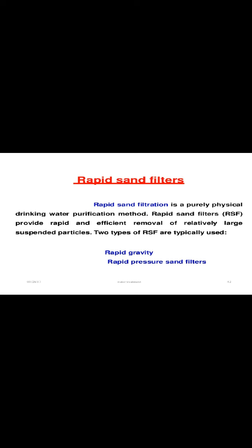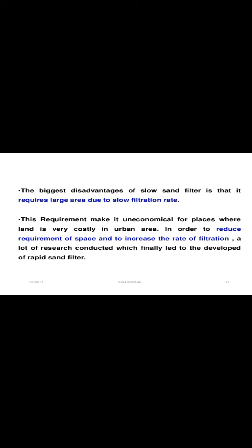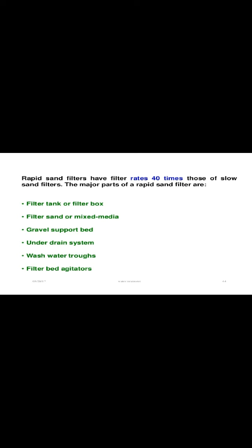Rapid sand filters provide rapid and efficient removal of relatively large suspended particles — a purely physical drinking water purification method. The two types of rapid sand filters are rapid gravity filters and rapid pressure sand filters. The biggest disadvantage of the slow sand filter is that it requires a large area due to its slow filtration rate, making it uneconomical where land is costly. Rapid sand filters have filtration rates 40 times those of slow sand filters. The major parts include a filter tank, filter sand or mixed medium, gravel support bed, under-drain system, wash water troughs, and filter bed agitators.